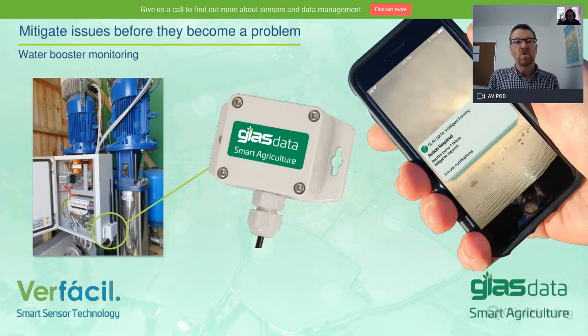This one is a water boosting application. Boreholes are often distant from farm buildings, and problems are only brought to attention when the storage tank is empty. We've installed a static pressure sensor on the borehole pump output to ensure the correct water pressure is provided, and we've also put water level monitoring, the same sensors as this again, in the water tanks. So we're getting it at both ends. We're getting it from the borehole. We can check the pressure, but we also check the water level as well.